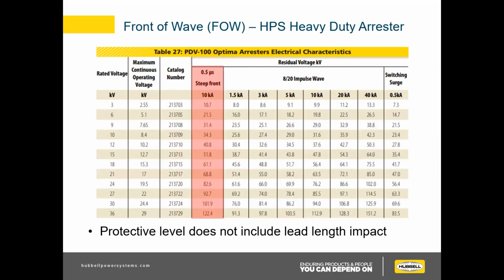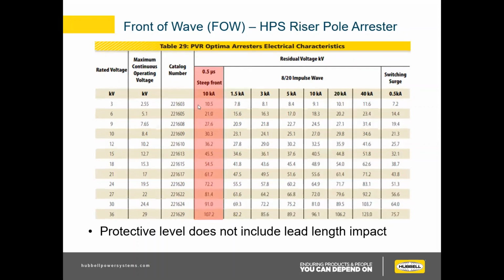As you can see, I'll go back for a second. This is our heavy duty arrestor, our PDV100 discharge voltage. There's not a whole lot of difference between the heavy duty and the riser pole, as you can see here, at lower voltages, at 3, 6, 9, up to about 12. But after you get to 12, this is where the riser pole really tends to shine a little bit and has a good bit lower discharge voltage. That makes a big difference when you double it. So that's another thing to consider.